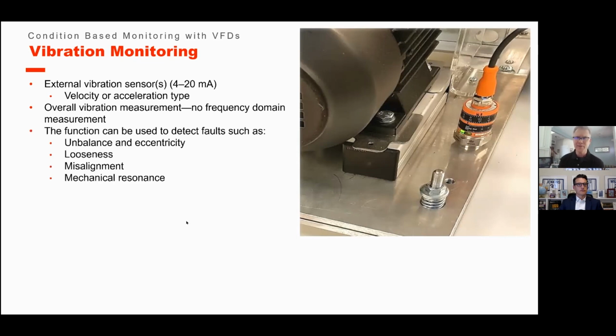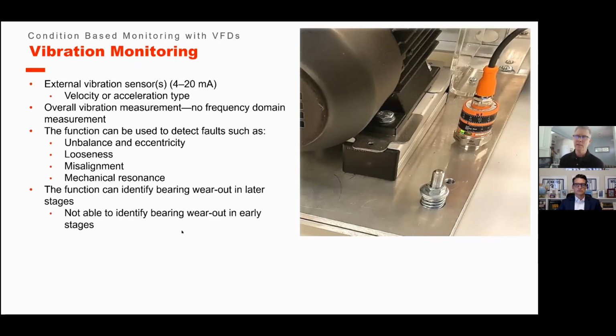Vibration happens at all different levels. Drives have skip frequencies in them because there are resonances, and those vibrations, heavy vibration, can happen. Extreme heavy vibration can actually destroy the fixture. Let's say a fan, for instance, that's not exactly weighted or has a weird vibration at a certain speed range. So it happens at different spots. The function of this is really on vibration to check for any type of unbalance, looseness, misalignment, any type of mechanical resonance you're going to run into. And you have capabilities with the drive to work around those resonances.